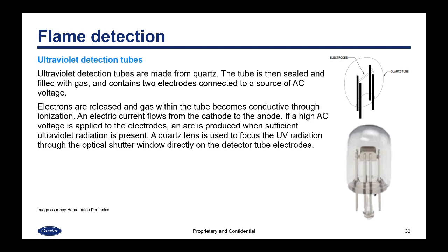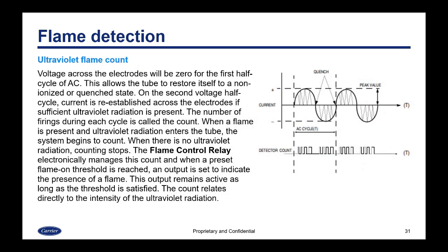A quartz lens is used to focus UV radiation through the optical shutter window directly on the detector tube electrodes. Voltage across the electrodes will be zero for the first half cycle of AC, allowing the tube to restore itself to a non-ionized or quenched state. On the second voltage half cycle, current is re-established if sufficient ultraviolet radiation is present. The number of firings during each cycle is called the count. When a flame is present and ultraviolet radiation enters the tube, the system begins to count; when there is no UV radiation, counting stops. The flame control relay electronically manages the count and when a preset flame-on threshold is reached, an output is set to indicate the presence of a flame. The count relates directly to the intensity of the ultraviolet radiation.